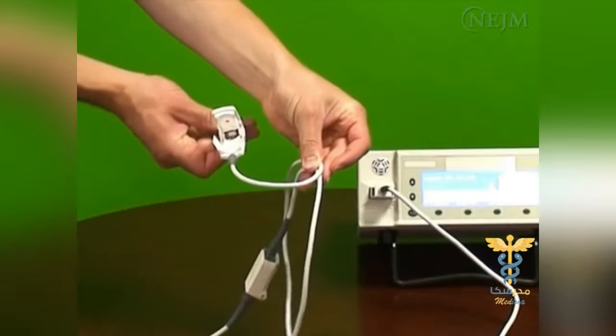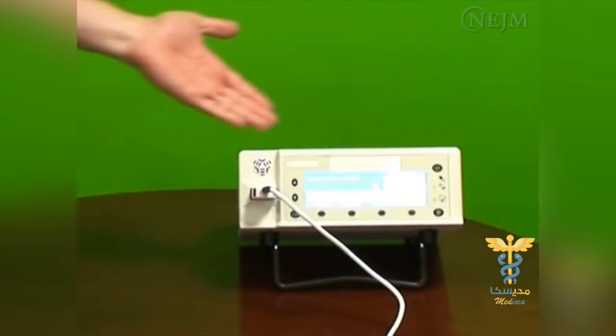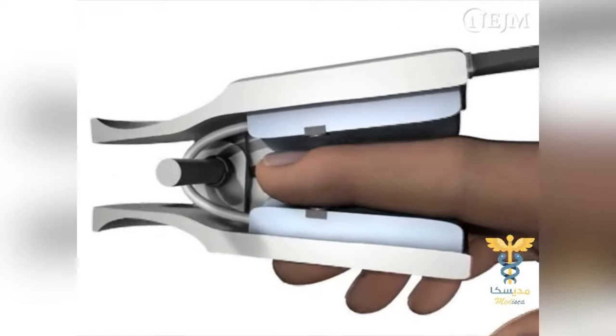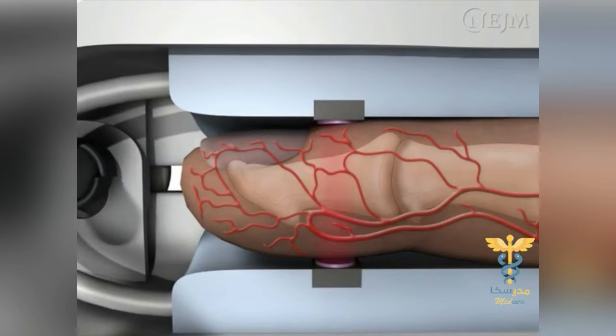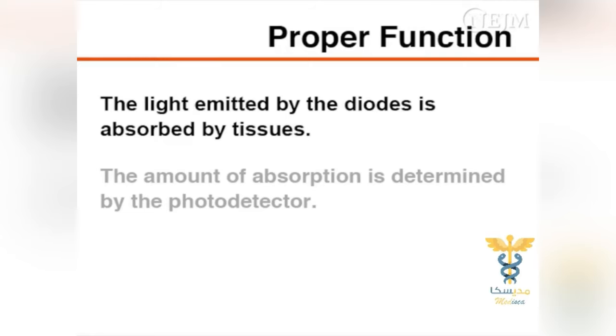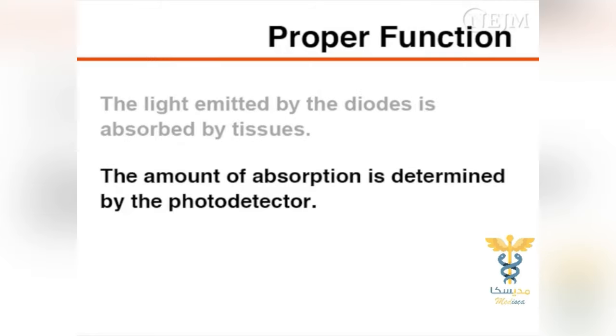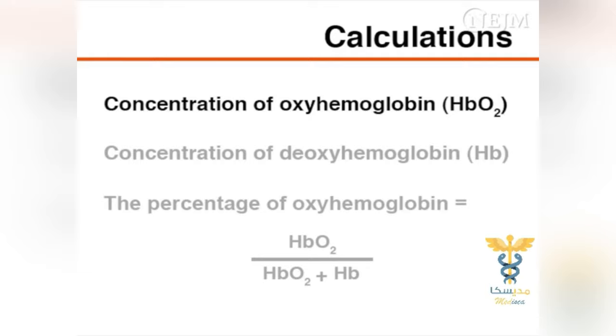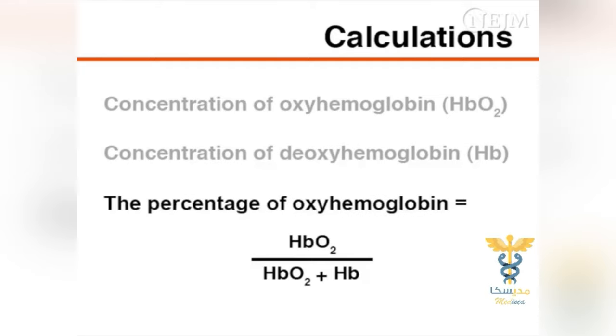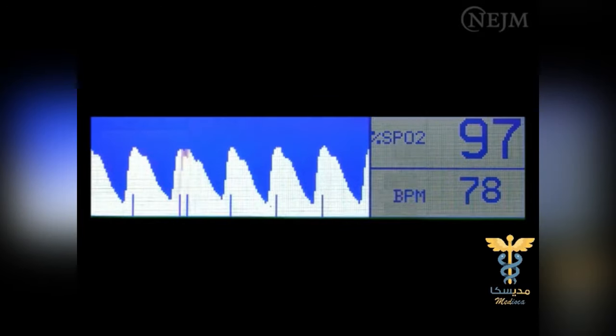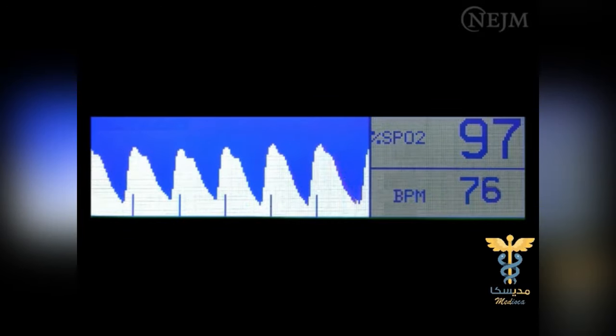Pulse oximeters consist of a peripheral probe and a small microprocessor unit. Traditionally, the peripheral probe contains a photodetector and two light-emitting diodes. The two light-emitting diodes emit light of different wavelengths. The light emitted by the diodes is absorbed by tissues, and the amount of absorption is determined by the photodetector. Using this information, the microprocessor determines the concentration of oxyhemoglobin and deoxyhemoglobin, then calculates the percentage of oxyhemoglobin and displays the hemoglobin oxygen saturation in arterial blood, a waveform corresponding to the pulsatile flow in arterial vessels, and the heart rate.